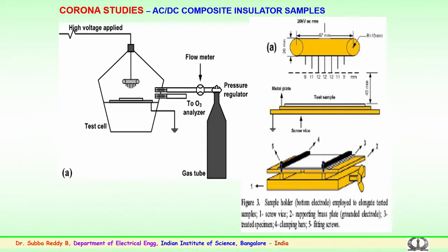So, corona studies are done for both AC and DC on composite or polymer insulator samples. It is normally conducted in an experimental test cell, where corona is intentionally generated with corona needles. Various types of needles could be used, either circular needles which are uniform in nature, or non-uniform needles which look like a comb-type electrode. So, uniform or non-uniform corona can be simulated by properly selecting the needles, and the test sample will be kept here, and high voltage is applied continuously.